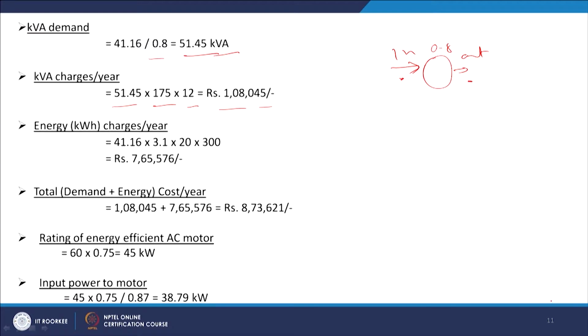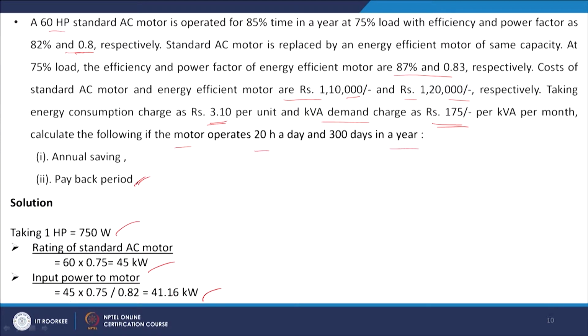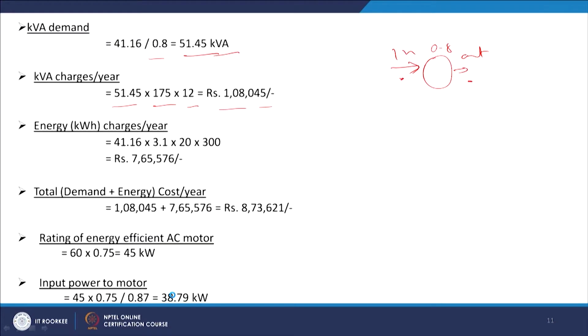And energy charges, so how much energy is it using? 41.16, we are using this energy. So, this into 3.1 per unit, and we have 20 hours a day, and 300 days per annum. So, this is the total amount for electricity charge. So, demand plus energy charge, or cost per year, is this amount plus this amount. So, 7,65,576 plus 1,08,045. If we add, 8,73,621, we are getting this much total expenditure for the standard motor.